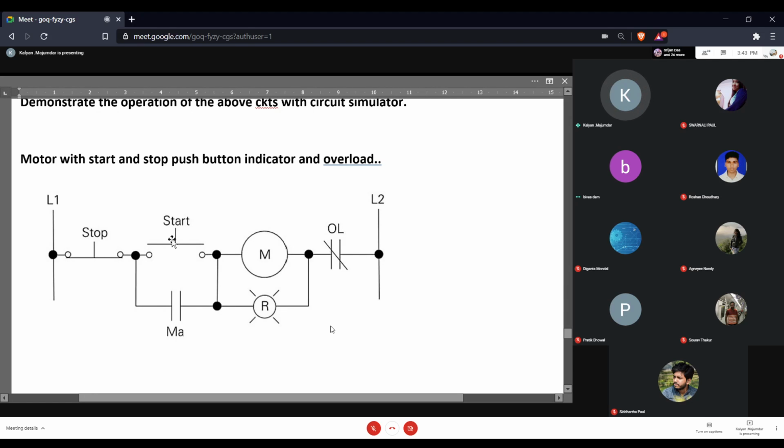যখন আমি স্টার্টটা ছেড়ে দেব, remember this is a push button. It's a momentary switch. So আমি যতক্ষণ চেপে রাখলাম তো fine, the relay is activated, your motor is getting power and the motor is rotating. যেই মুহূর্তে I release the start switch, what happens? তাহলে again the circuit breaks. Circuit break হলে আর এই কন্ট্যাক্টরটা পাওয়ার পাবে না, কন্ট্যাক্টর বা রিলে কয়েলটা পাওয়ার পাবে না. Relay coil, if it's not energized, then again the circuit breaks and your motor stops.